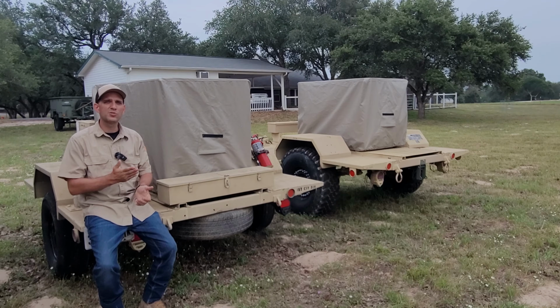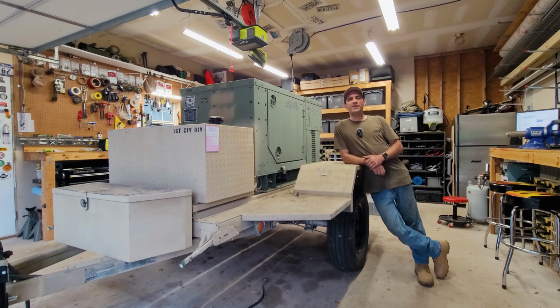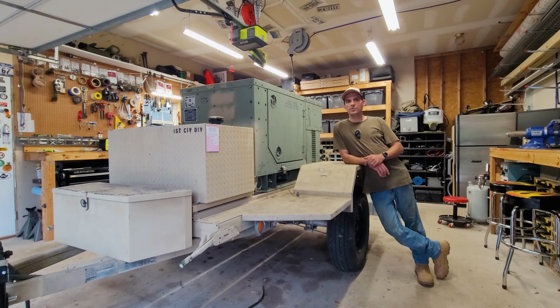All right, the generator's back in the shop. It failed my 6 hour test at about 2.5 hours. So I need to do some work on this, but really the point of what I needed to do for the video was show you how to set yourself up and do the 6 hour load test. That's the whole point of this, the point getting across. But I don't need to show you my 6 hour load test passing. The point is you know what to do.